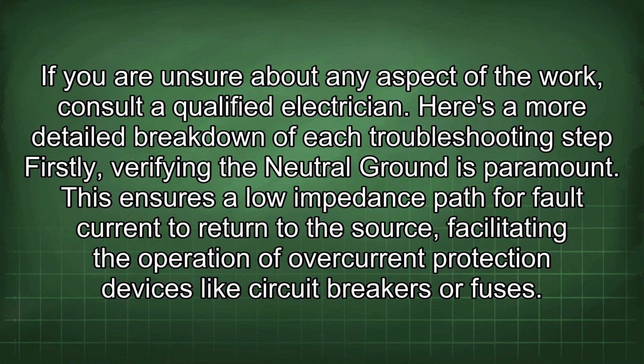Here's a more detailed breakdown of each troubleshooting step. Firstly, verifying the neutral ground is paramount. This ensures a low impedance path for fault current to return to the source, facilitating the operation of overcurrent protection devices like circuit breakers or fuses.